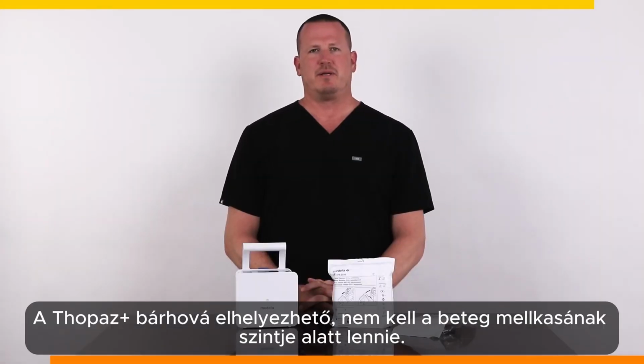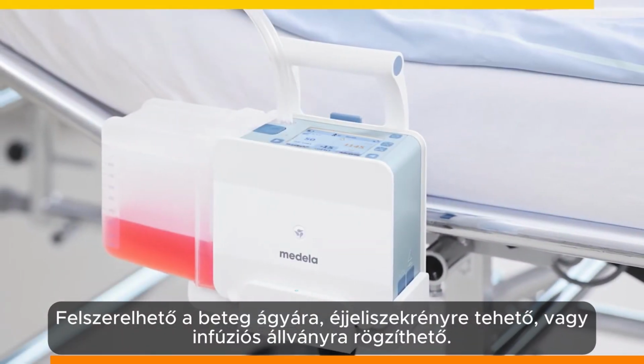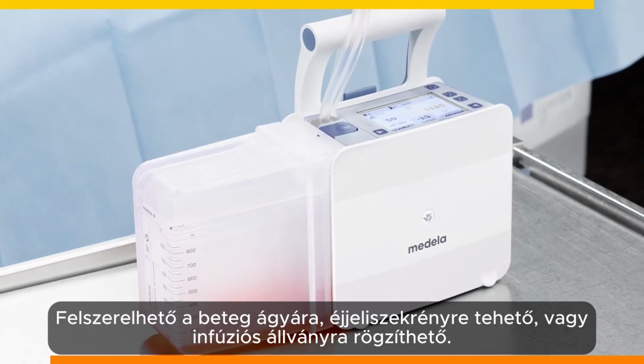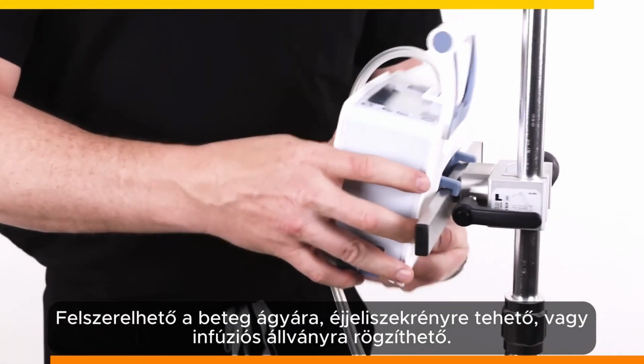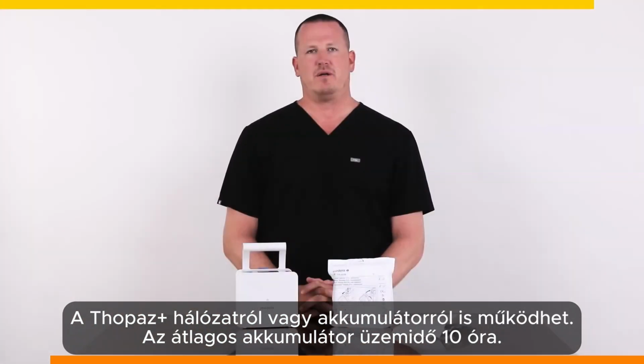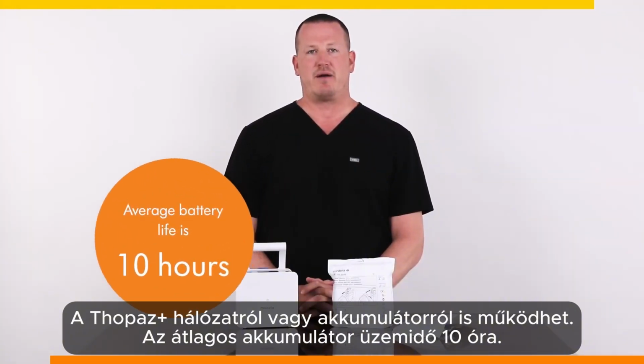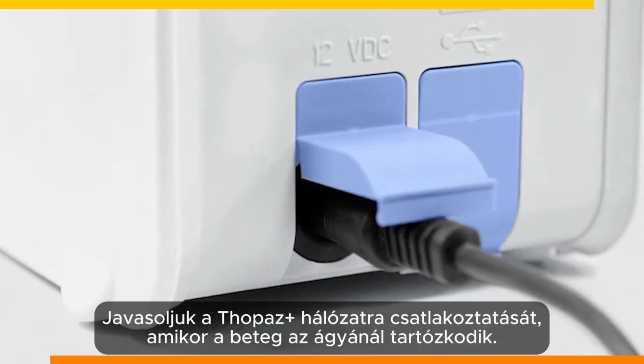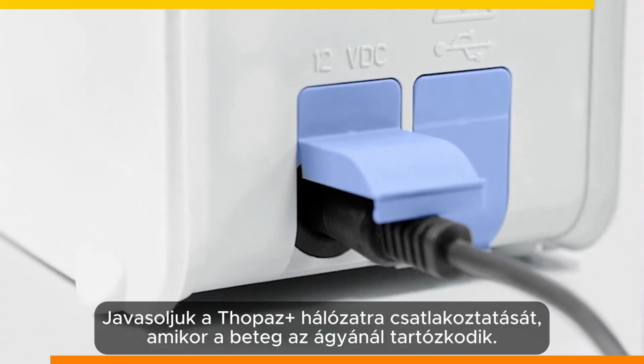The Thopaz+ can be placed anywhere, and it does not need to be below the level of the patient's chest. It can be mounted on the patient's bed, placed on a bedside table, or mounted on an IV pole. The Thopaz+ can run while it's plugged in or on battery power. The average battery life is 10 hours. We recommend plugging in the Thopaz+ whenever the patient is at the bedside.